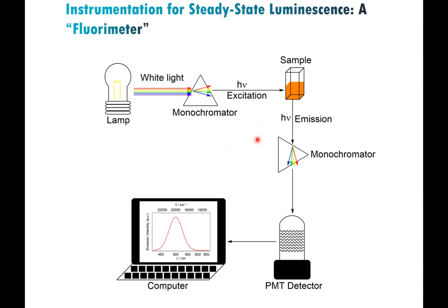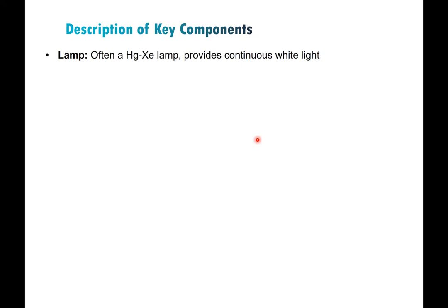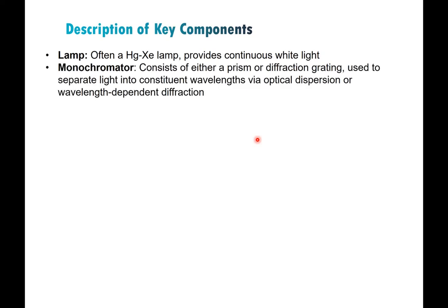The most common type of lamp is a mercury-xenon, which provides intense continuous light. Monochromators are very important on both the excitation and detection sides, and they'll be either a prism or a diffraction grating — all modern instruments use diffraction gratings. They separate light into constituent wavelengths. If you've ever held a prism up to sunlight and seen it produce a rainbow by splitting light into all the different wavelengths, that's basically what's happening in the monochromator — working via optical dispersion or wavelength-dependent diffraction.